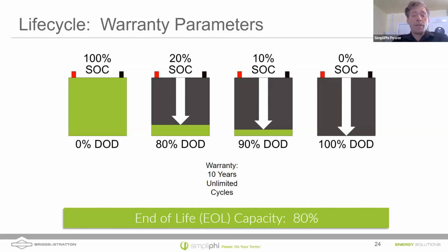And really, we know that there's a mixture that happens here, right? So Daniel's saying, if you've got your batteries and you just have them for backup, discharging them down to 100% depth of discharge, taking all the energy out of there thousands of times, it's not going to create immediate damage. But if you want the longest life out of your battery, we recommend sizing it to an 80% depth of discharge, and that's where we're expecting that 10,000 cycles.